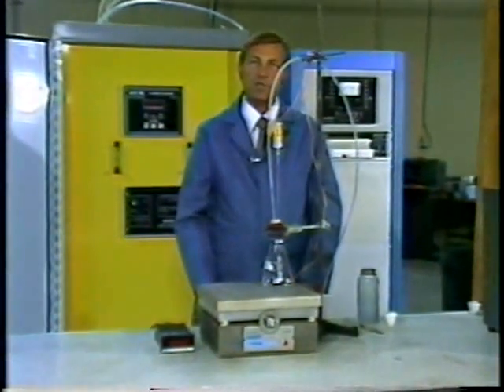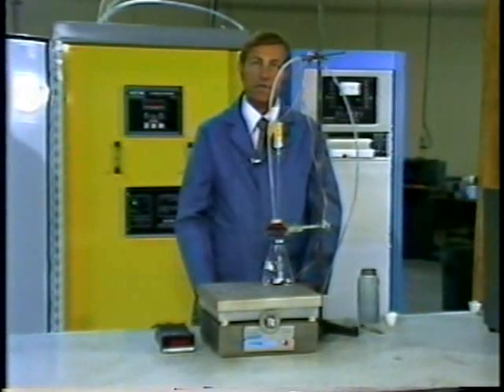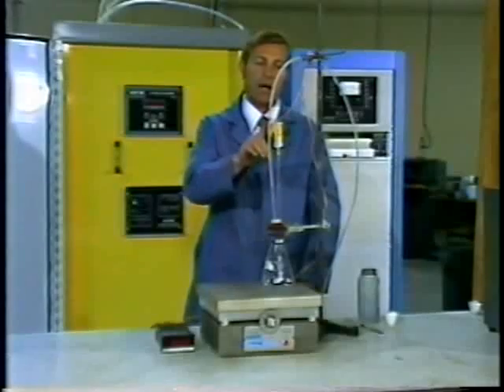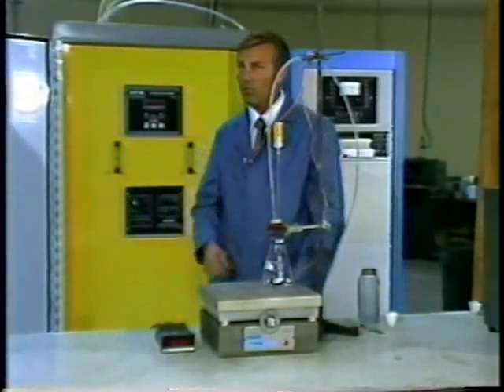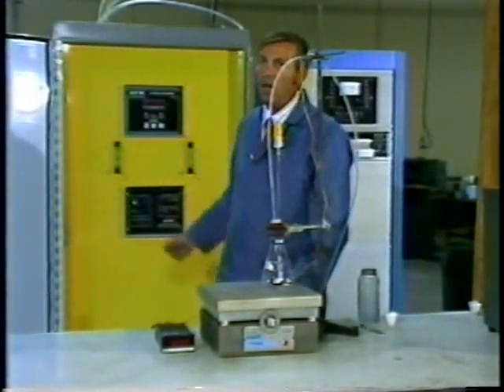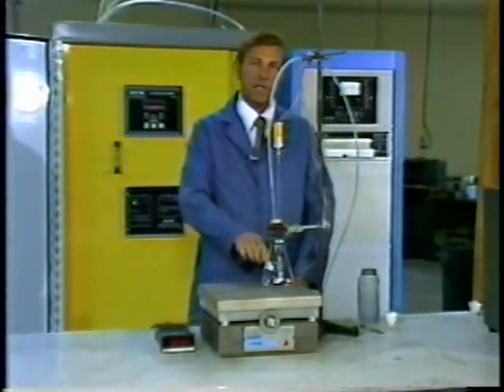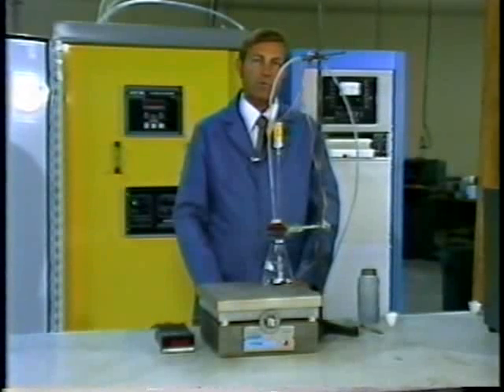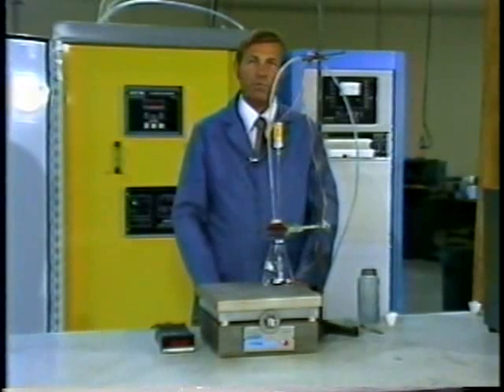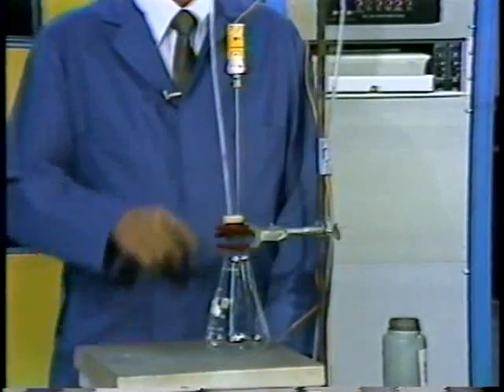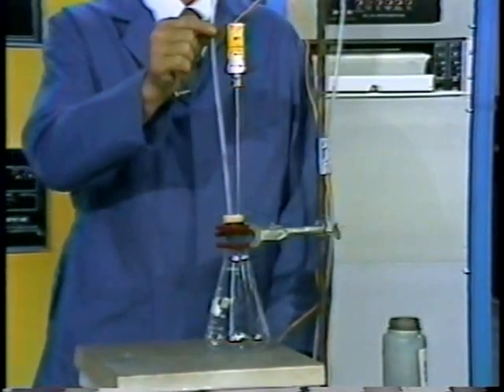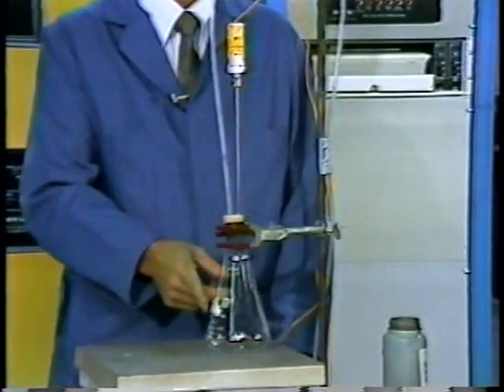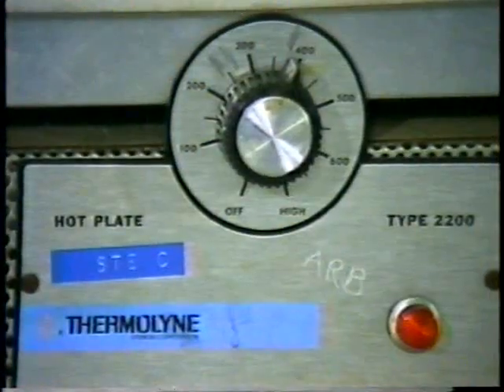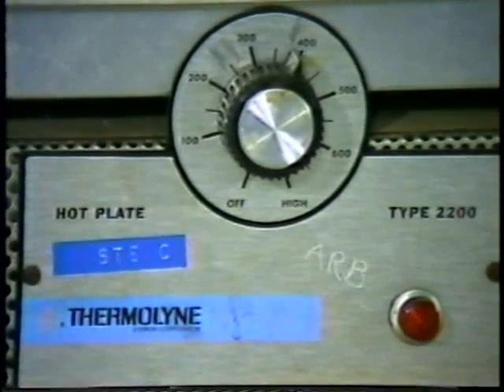A simple demonstration will show the difference in sensitivity to oxidation between a thermocouple and the KVB coal fire protection system. We can create a condition of spontaneous combustion similar to that which may take place in a mill when the flow of air and coal is interrupted, causing coal accumulation and self-heating. Both a thermocouple and a CO probe are placed into this flask that has been heated to a normal mill operating temperature on this hot plate.